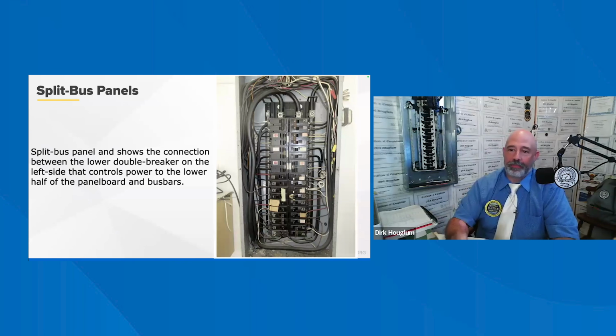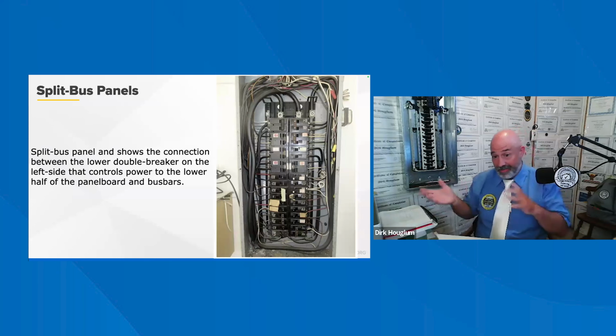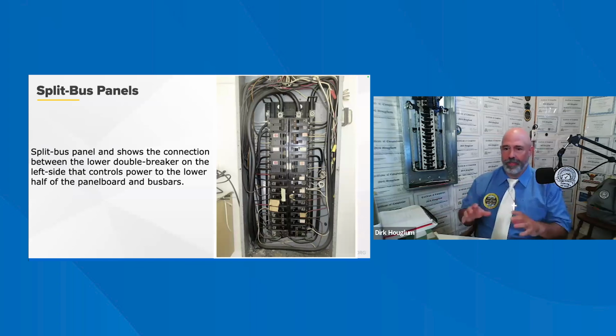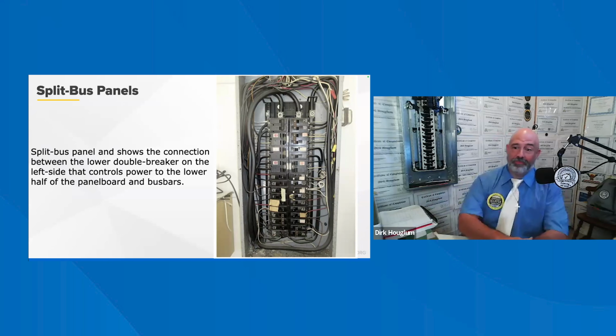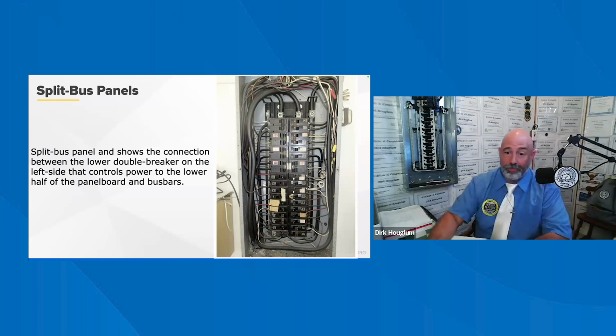When home inspectors see these split bus panels, they should count how many throws are required to turn off the panel. More than 6 throws are usually found where someone has added a circuit to a full panel by adding a double breaker, tandem, piggybacking, and all that other stuff. That changes the number of disconnect throws from 6 to 7, and that's the defect. There is no requirement to replace existing split bus panel boards. Allowed to install 120-volt breakers in the top 240-volt portion of that panel.